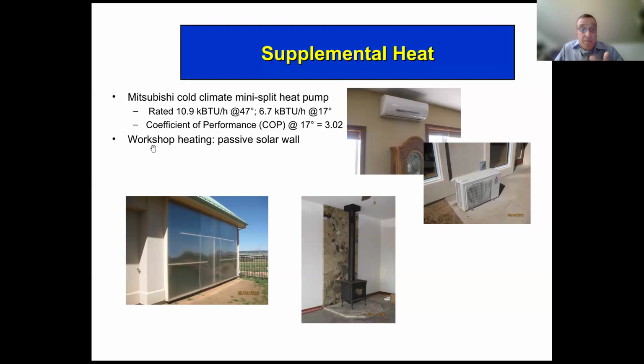And that heat pump is rated, let's talk about 17 degrees Fahrenheit at 6.7 thousand BTU per hour. This particular Mitsubishi unit is a cold climate Mitsubishi, so it's actually rated all the way down to -5 degrees Fahrenheit. Although the performance drops, the coefficient of performance drops below 3 when you get down to 5 degrees.